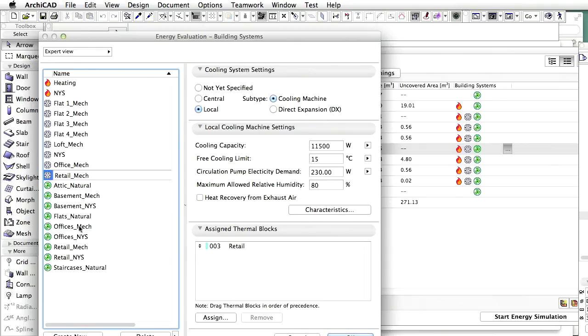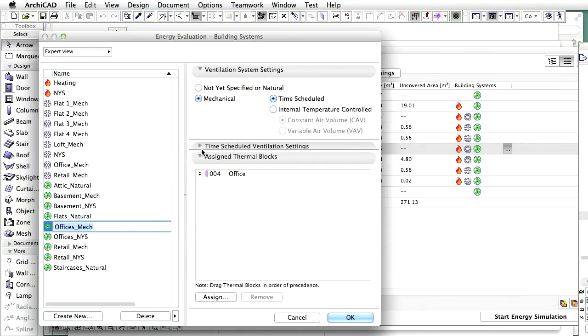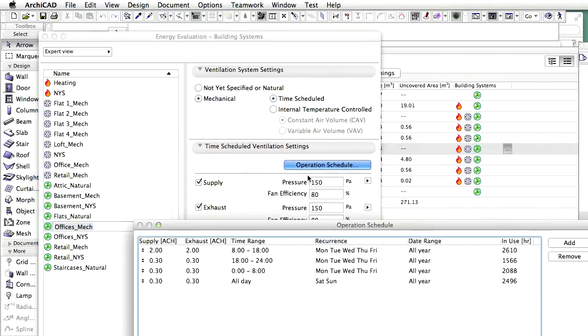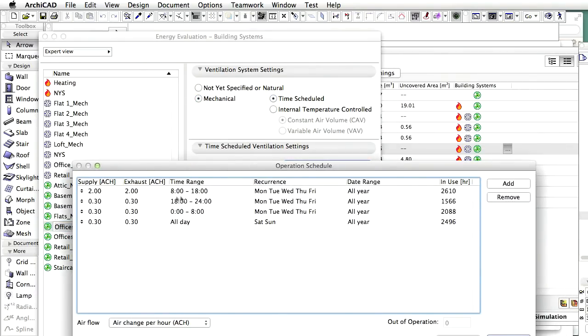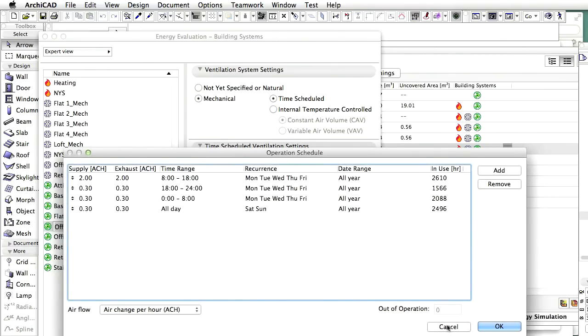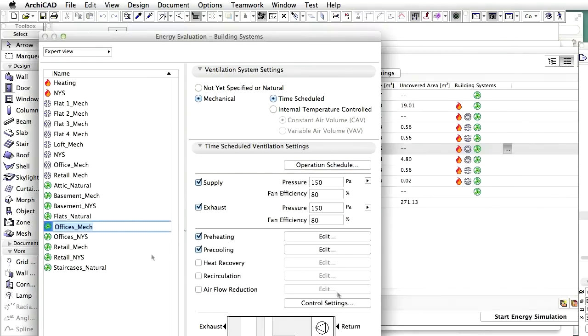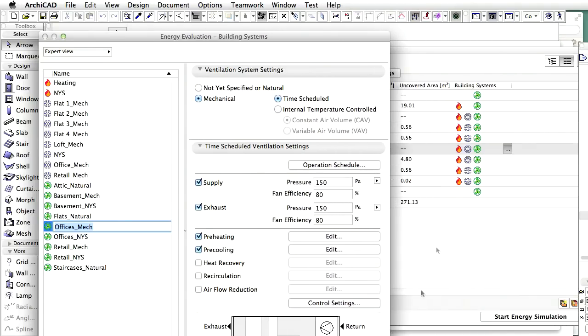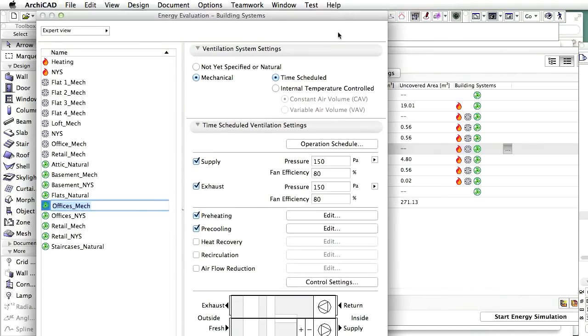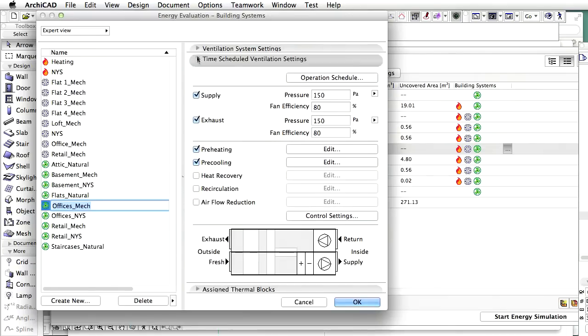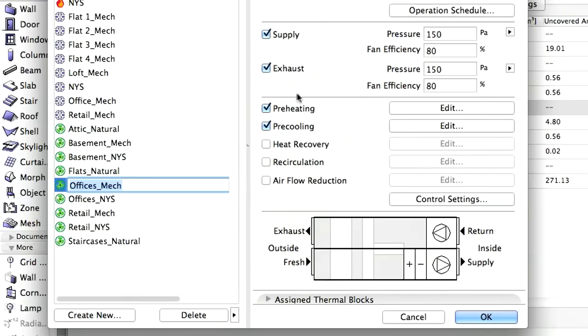Let's review the settings of the ventilation system assigned to the thermal block with an office operation profile. Use the time-scheduled ventilation settings chapter of the Building Systems Dialog in expert view if you wish to modify the default time-scheduled mechanical ventilation system parameters. Details such as supply and exhaust fan pressures and efficiencies can be altered, and pre-heating and pre-cooling parameters can be specified. It is also possible to model more advanced ventilation systems using the heat recovery, recirculation or airflow reduction dialogs.